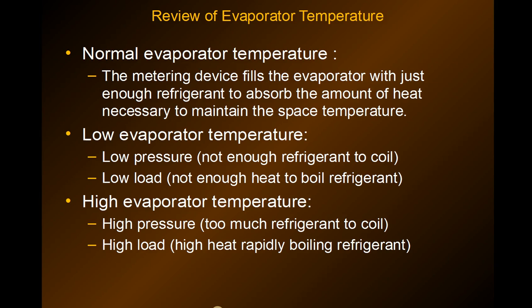What happens when you have a low evaporator temperature? That's caused by not enough refrigerant in the system, which gives you low pressure, or a low load, meaning there's not enough heat to boil off the refrigerant. High evaporator temperature is caused by too much refrigerant — an overcharged system — or a high heat load, which causes the refrigerant to boil off too rapidly.